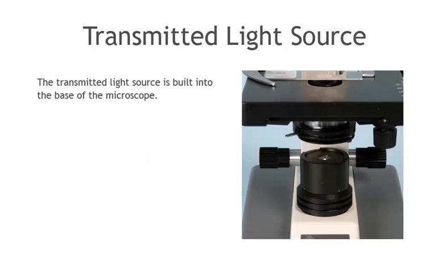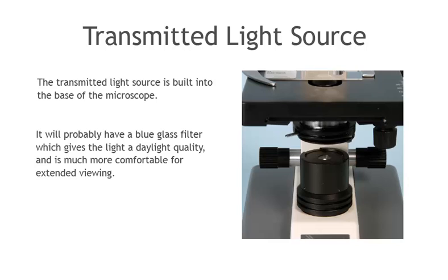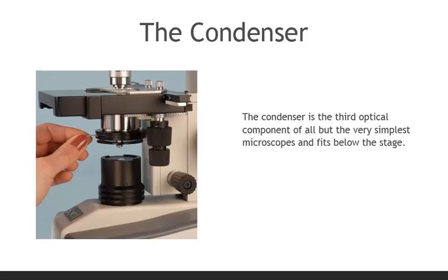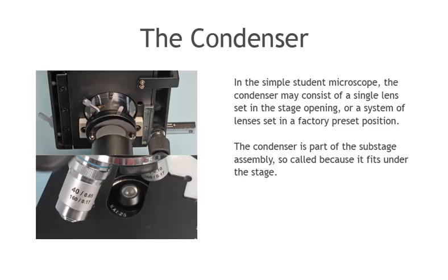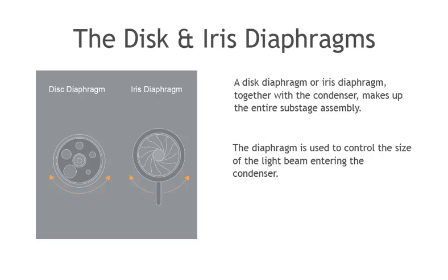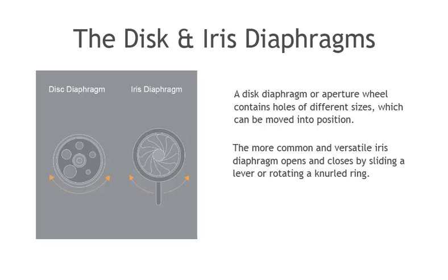Let's follow the path of transmitted light rays through a typical student microscope, discussing the function of each component in turn. The transmitted light source is built into the base of the microscope. It will probably have a blue glass filter, which gives the light a daylight quality and is much more comfortable for extended viewing. The condenser is the third optical component of all but the very simplest microscopes, and fits below the stage. In the simple student microscope, the condenser may consist of a single lens set in the stage opening or a system of lenses set in a factory pre-set position. The condenser is part of the substage assembly, so called because it fits under the stage. A disc diaphragm or iris diaphragm, together with the condenser, make up the entire substage assembly. The diaphragm is used to control the size of the light beam entering the condenser. A disc diaphragm or aperture wheel contains holes of different sizes, which can be moved into position.